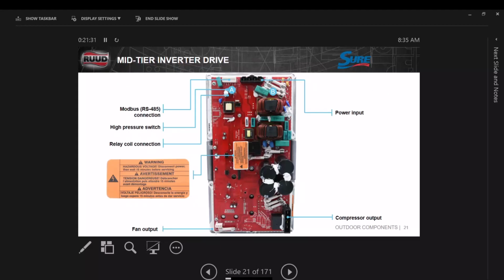Here's our power input to the inverter board here at the top. 208, 230 volt, single phase, plus or minus 10%. Then you have that RS485 plug there. That's the Modbus plug that brings communication back and forth to the board. Right below that, we have our high pressure switch. We have our relay coil connection. The relay coil is a solenoid coil that equalizes the pressure on the compressor, and we'll show you that here in a minute. Bottom is where the fan motor output is.